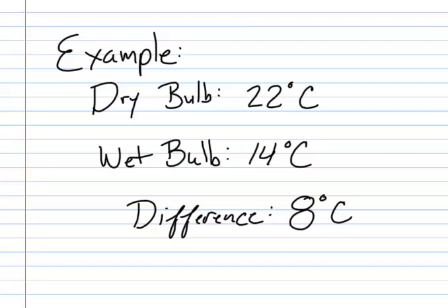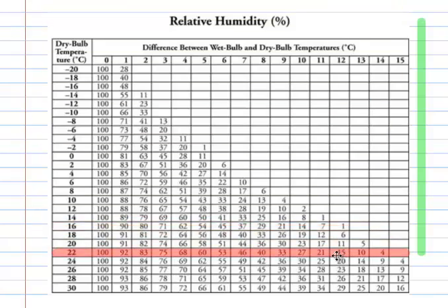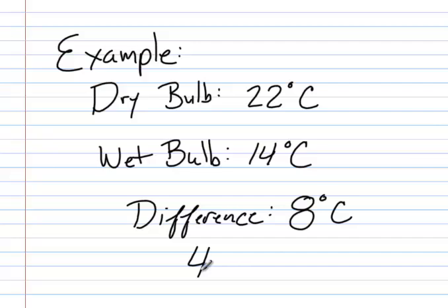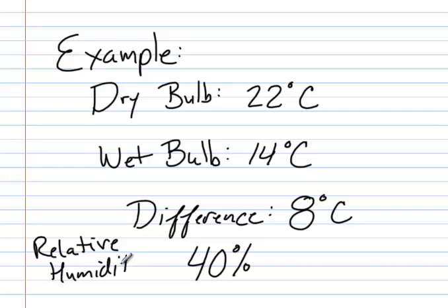Now it's time to flip over our lab and look at the chart on the back. We start by looking at our dry bulb temperature, which was 22 degrees, and then the difference in temperature between our dry bulb and wet bulb, which was 8 degrees. Looking on our graph, at 22 degrees and a difference of 8 degrees, the relative humidity would be calculated at 40%.